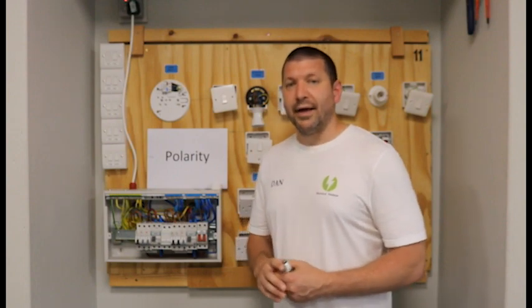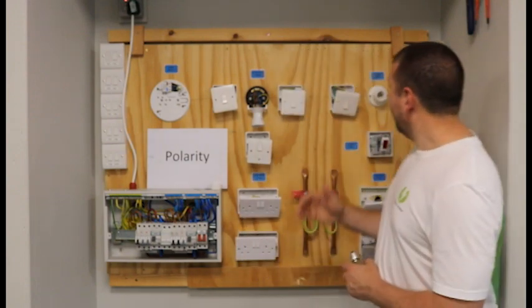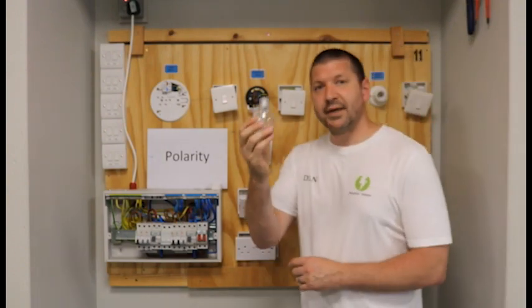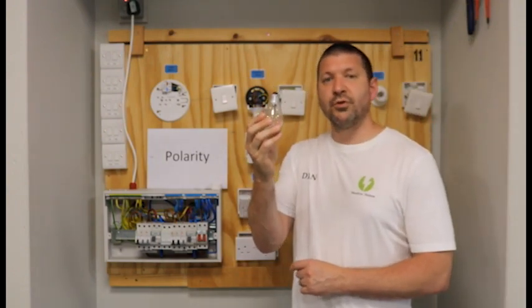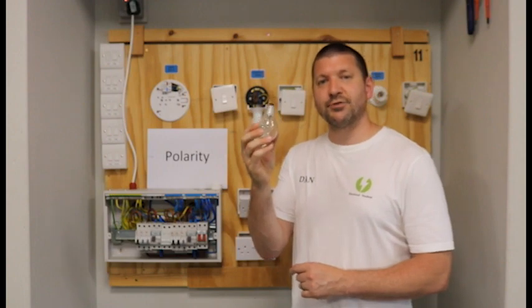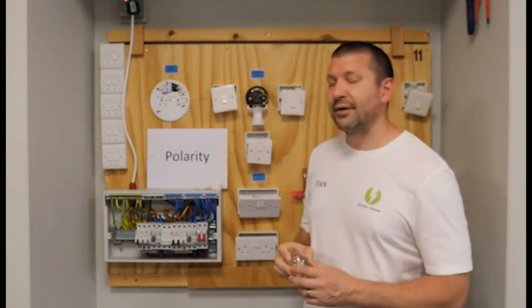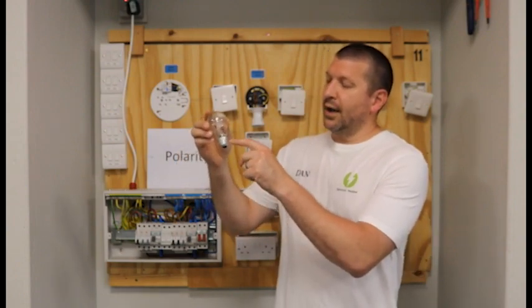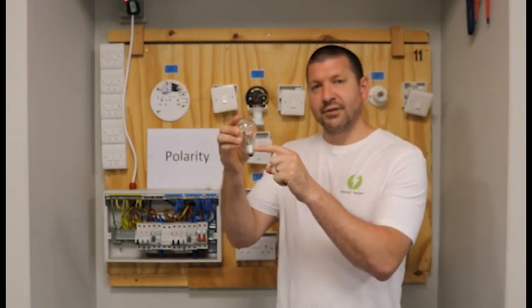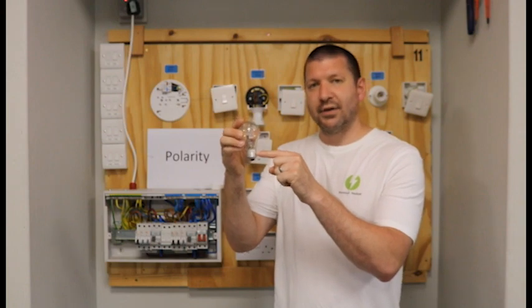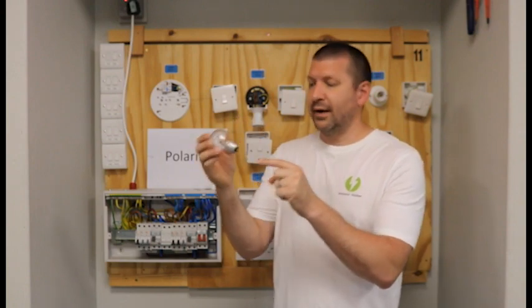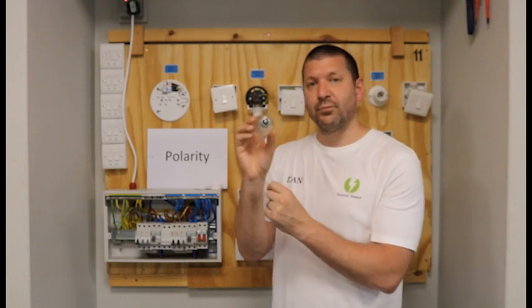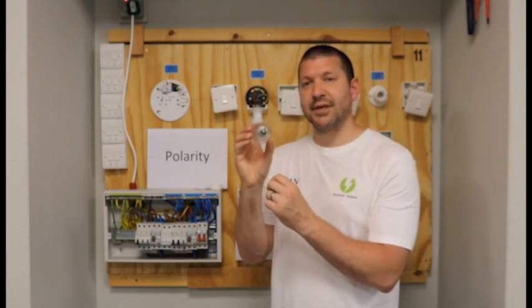Polarity test B is very specific to this type of lamp holder. These old school screw lamps, the ES, Edison screw lamps. Polarity test B ensures that we have got the outer connector, this thread connection is to the neutral and the centre pin contact is to the live. We must ensure that, that's polarity test B.